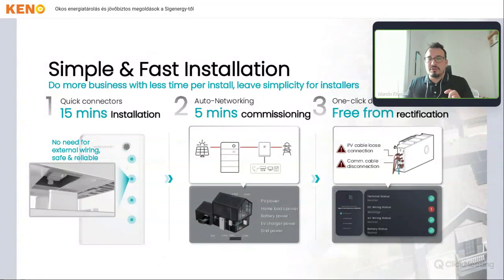So then the commissioning. Generally during commissioning, we just scan the QR code on the right-hand side of the inverter through the app, called My Sigen app. On this app you can just add the new system. This is crucial for very fast commissioning. Generally the time on site, even for a megawatt hour scale project, is like 15 minutes to commission the whole system.